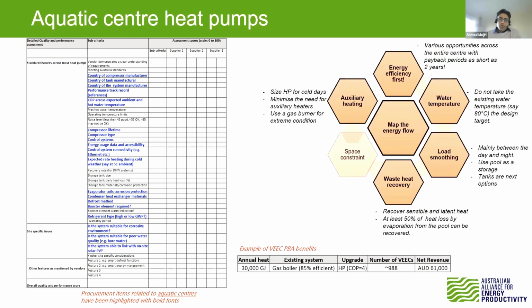There are lots of opportunities for waste heat recovery in an aquatic centre, which we have discussed in the guide. One important point is that there is a huge amount of latent heat in the exhaust air from aquatic centres. Several analyses have shown that at least 50% of the heat loss due to evaporation from the water surface can be captured by heat pumps, because they are able to condense that moisture and capture its latent heat.